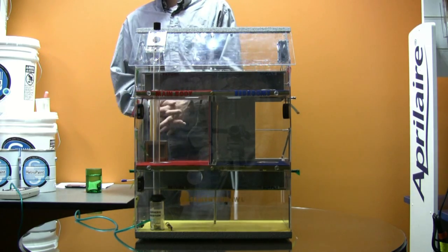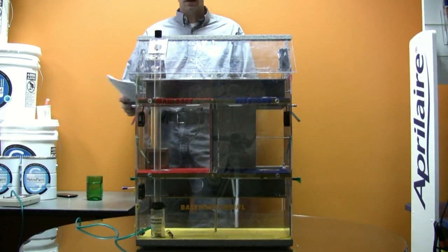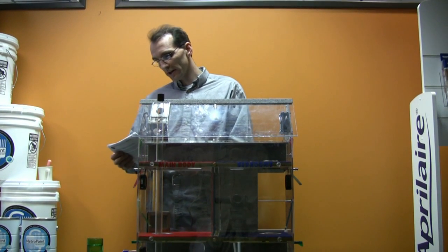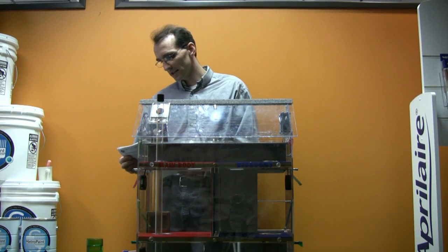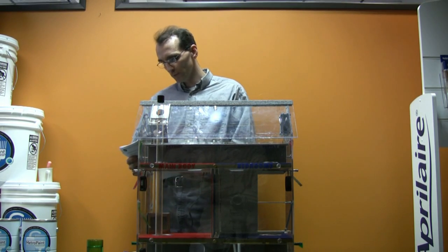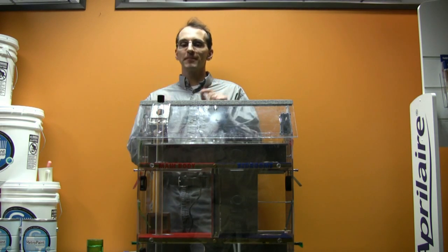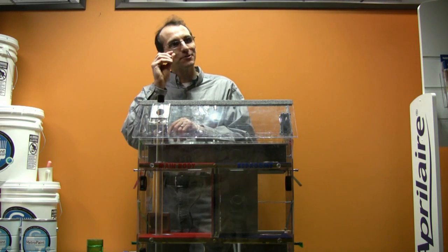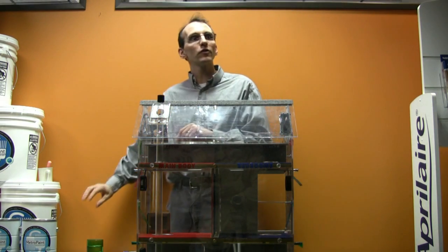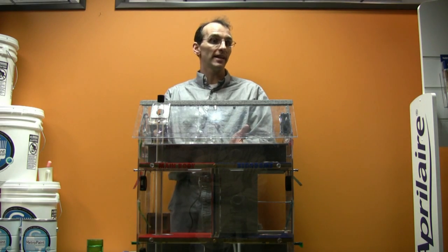Is 1.9 bad? There are tables that have been set up as standards in the industry over a long time, and I can tell you that for a natural draft water heater, the limit you can have in that area is minus 2. So we're at minus 1.9. In this test scenario, if we were another tenth of a pascal higher, we would be over the limit for what a worst case test could show, and we couldn't leave the house in that condition.